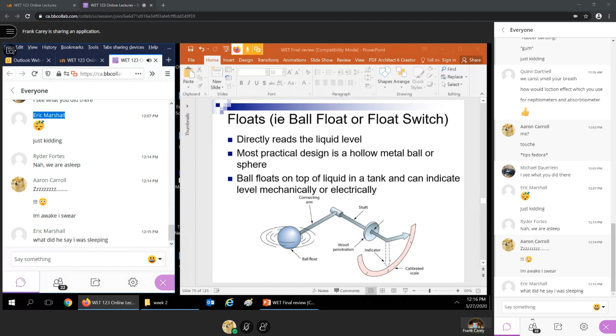Ball floats, by far the most widely used because of our toilets. Basically the ball just moves up and down based on the level. It floats on top, and it is used very often with electrical switches. Inside here is a conductive fluid, usually mercury, therefore they're getting out of favor, mercury switches. They used to be very common, they're not quite as common now. Just an example of how they work.